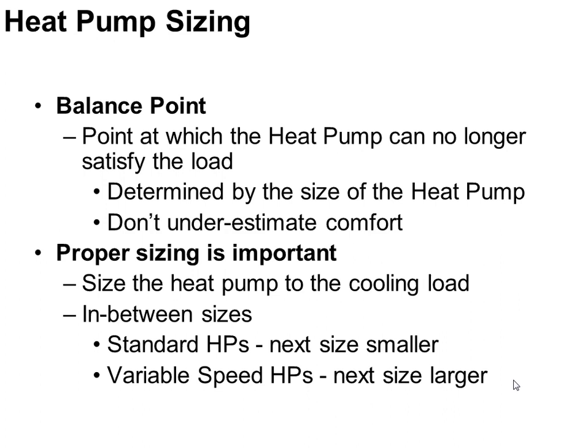So traditionally, we've sized heat pumps for the cooling load, right? So if you came up with, let's say, a 33,000 BTU cooling load, I'd either have to give you a 2.5 or a 3-ton heat pump. Hopefully, I would give you a 2.5 so I wouldn't be oversized.